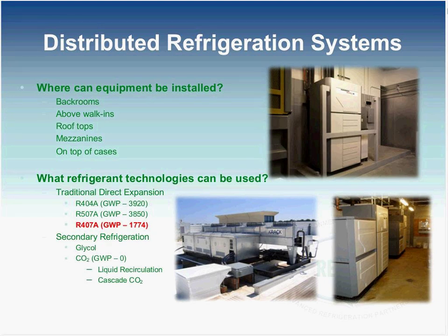That's correct. You do typically see them. Workers will have more access to them, but they are hidden from the shoppers and in back rooms above coolers and freezers, depending on how the store is laid out. Some stores have bakeries and kitchen areas in different parts of the stores, and it's not uncommon to have units above walk-in coolers and freezers spread out throughout the store. Again, to the benefit that you mentioned, having the refrigeration unit closely to the loads, and again, it does reduce the amount of refrigerant charge that you have.